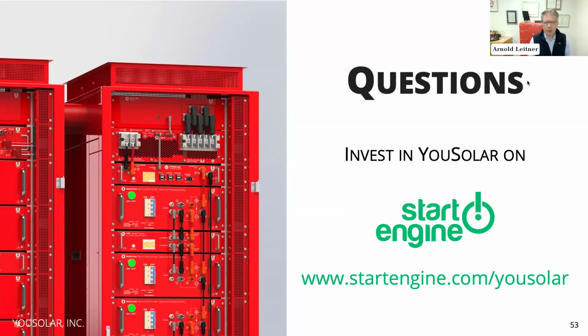Space needs for the PowerBloc: they are about 26-something inches wide, 32 inches deep, and 7 feet tall, 87 inches tall with the vent hood you see here on the right-hand side. There should be 6 inches spaced apart - that's the requirement from the fire departments. We also like them 6 inches off the wall for similar reasons, and then 12 inches on the right and left side for conduit to come out. The PowerBloc itself has no conduit between units - everything connects through a kind of plenum, which you see in this picture. So there's no external conduit, whether you have a 2-unit PowerBloc, which we call a base, a 2-cabinet PowerBloc, or 8 cabinets. We lay out the floor, and the PowerBloc is put on top of those bases.